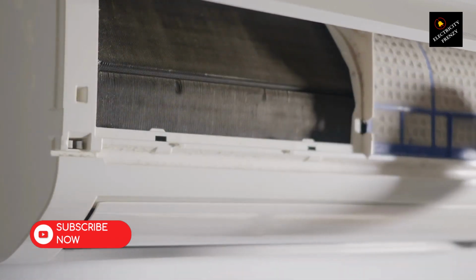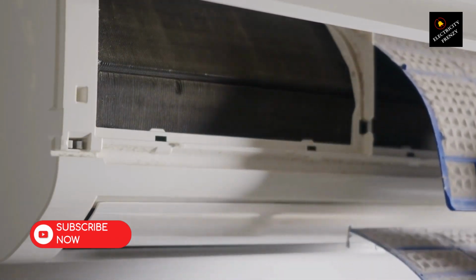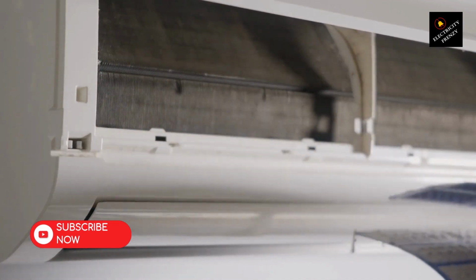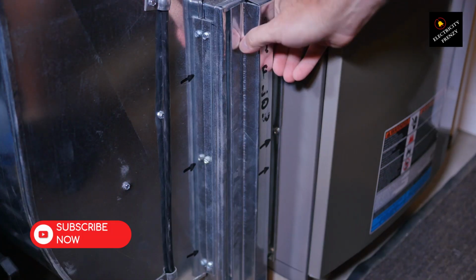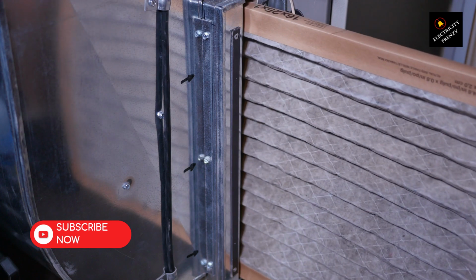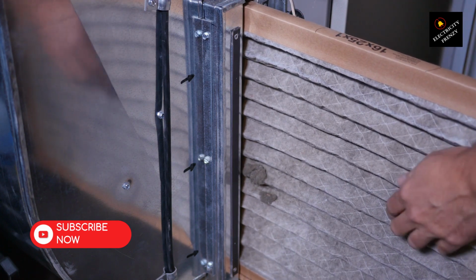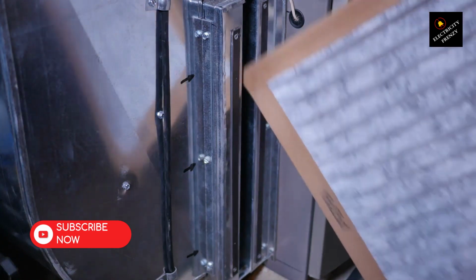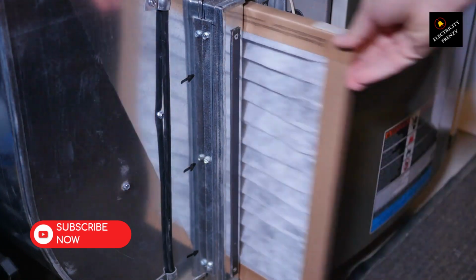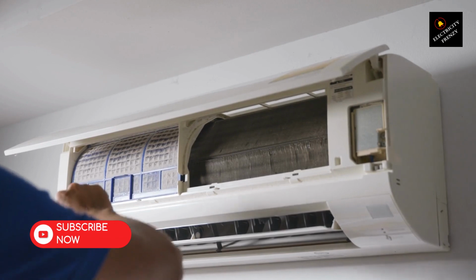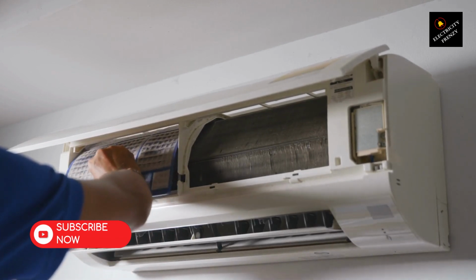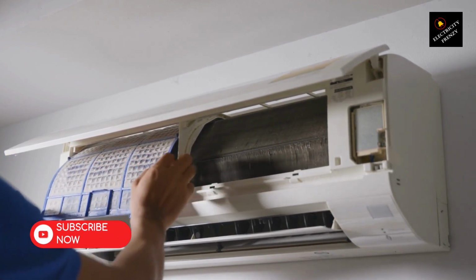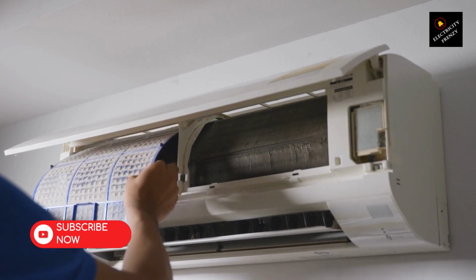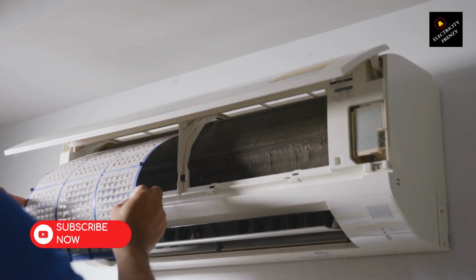Another possibility is a refrigerant leak or low levels. When your air conditioner lacks sufficient refrigerant, the compressor compensates by drawing more current, potentially causing the breaker to trip. Diagnosing a refrigerant leak or low levels requires professional expertise and specialized equipment. A licensed HVAC technician can perform a pressure test and inspect the system for leaks using a refrigerant leak detector. They will also measure the refrigerant levels to determine if they are within the manufacturer's specified range.